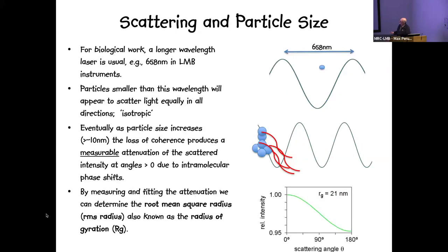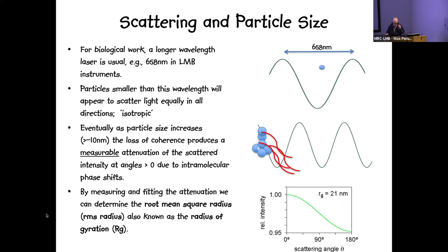Normally in biological work we use a wavelength in the red region — in the case of LMB instruments, it's 658 nanometers. The reason is mainly to avoid any absorbance present in biological molecules. Particles smaller than this wavelength will appear to scatter light equally in all directions: so-called isotropic scatterers.